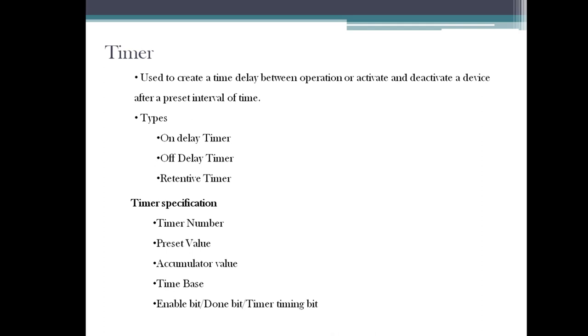That counting value or running value is stored in the accumulator. The fourth one is time base. How are we going to start counting - whether it is in seconds or milliseconds? Allen Bradley timer has a time base option. Time base is related to the resolution of the timer. The last parameters are enable bit, done bit, and timer timing bit.